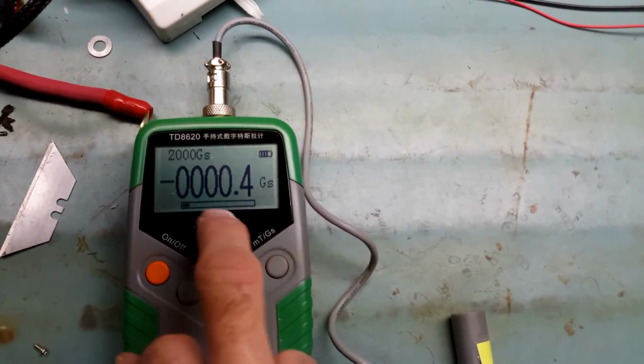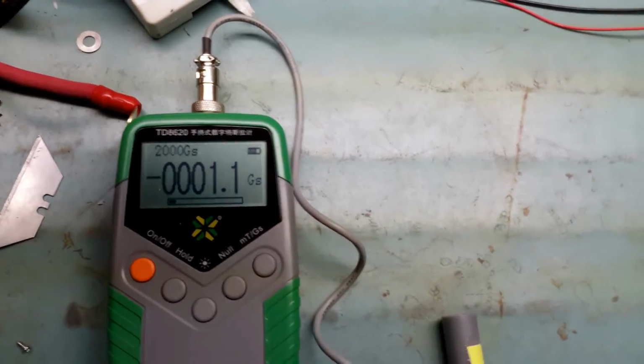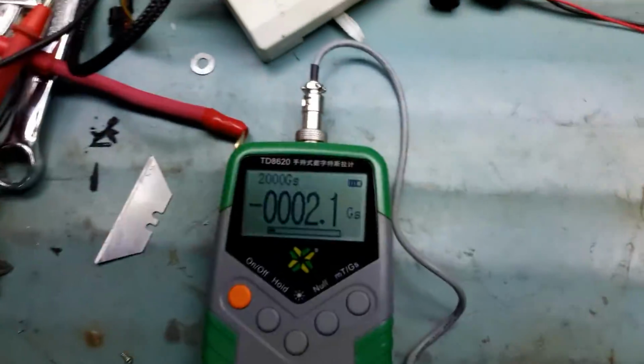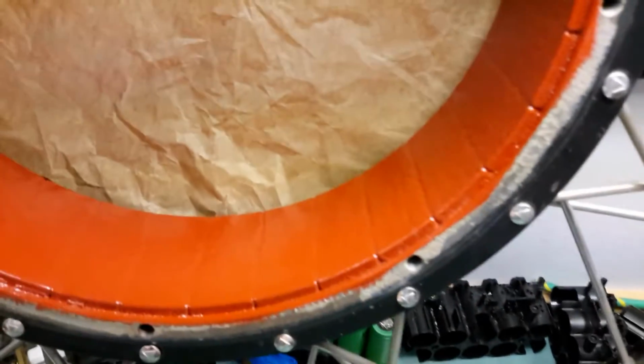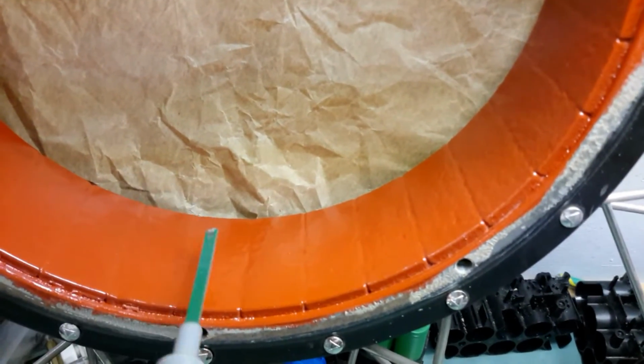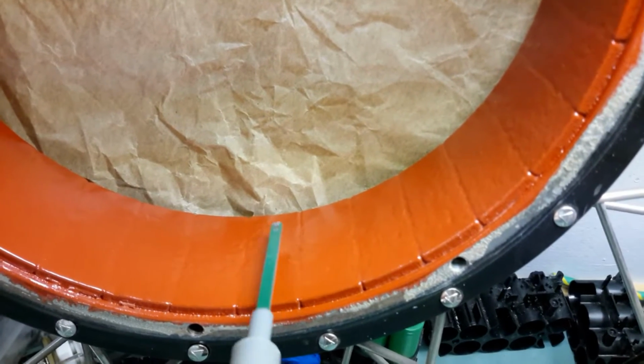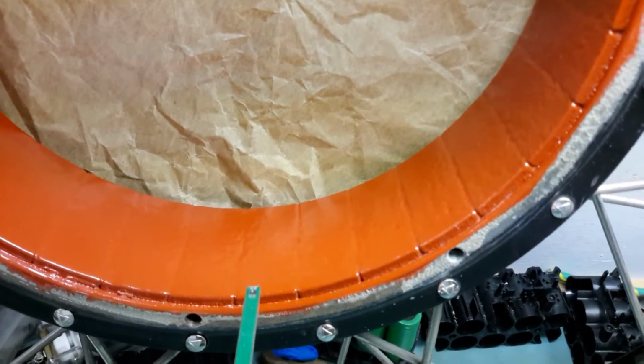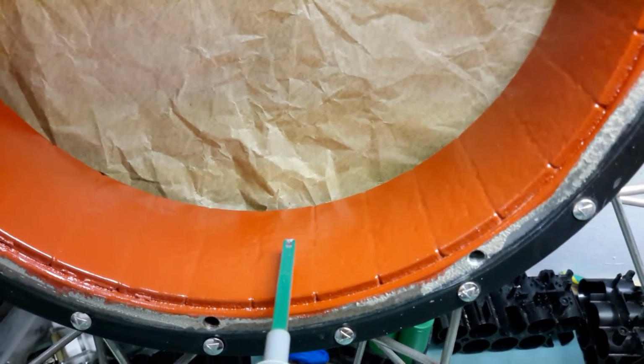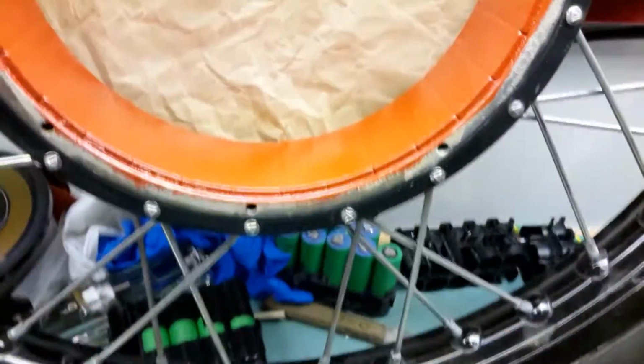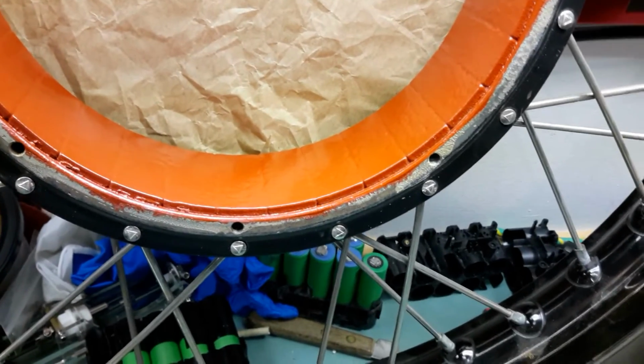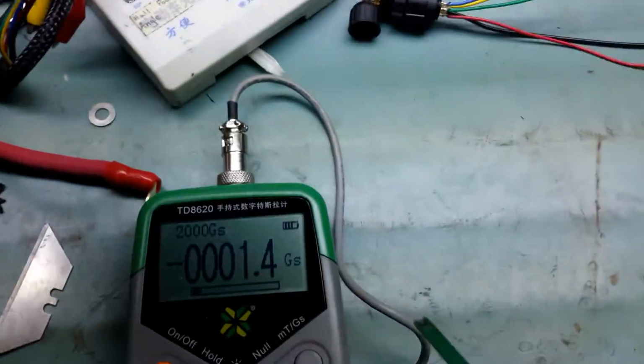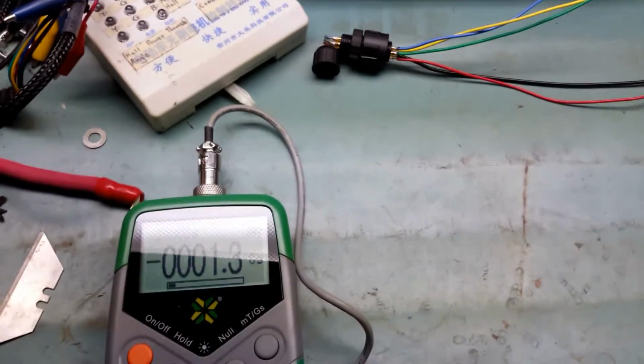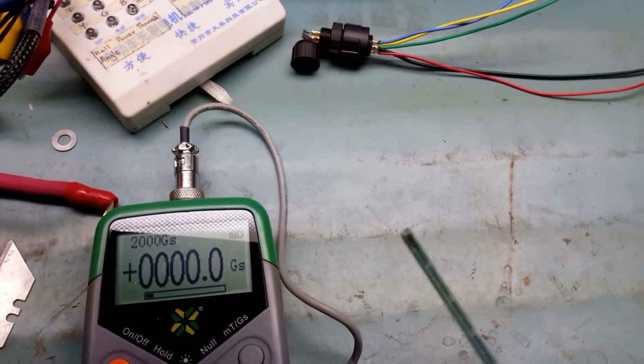And there's a bar graph to indicate when it will change the range, because the dot will change according to the range. Okay, so I will measure. I will indicate where I put it, and I will show you the data. So you see the magnet here. I will probably put it in the center of the magnet, as this is a location where the magnetic field is more uniform than on the edges, where it's slightly more intense. But I guess in the middle it will be accurate, as it's uniform and not a very isolated maximum on one area of the surface. So as you can see here, it still measures 1.4 Gauss negative, depending on the orientation I put it. Probably the magnetic field of the Earth, not sure, but I will just null it.